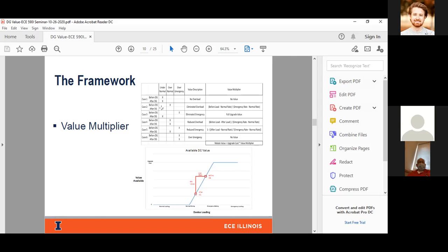If you take case 2, where you have an asset that is above the normal rating when you don't have DG, and then after you added DG, it actually helped and brought that loading down under the normal, then yeah, you do have value here, and you eliminated an overload. And the value multiplier is really the delta between the before and after normal rating divided by the difference, or delta, between the emergency and normal rating itself. Here's another case where before the DG, the asset was above the emergency rating, and then the DG was able to bring that asset all the way down below the normal rating. And here you're eliminating the emergency, and you get a value for the full upgrade that the utility would have paid in this scenario.